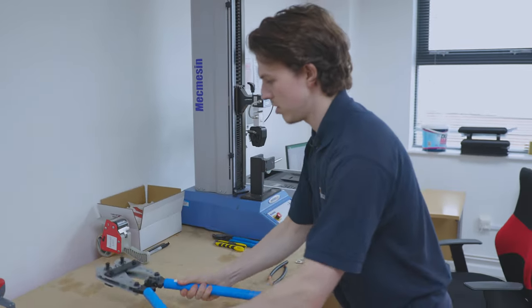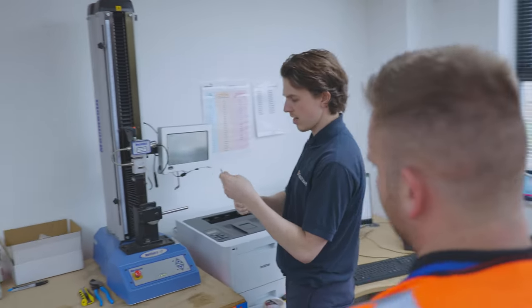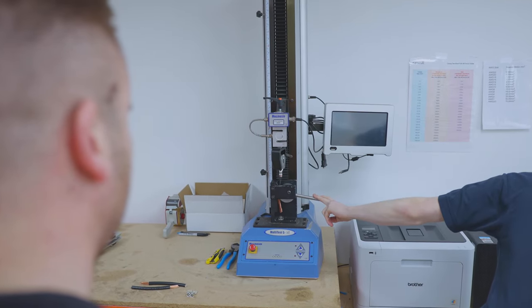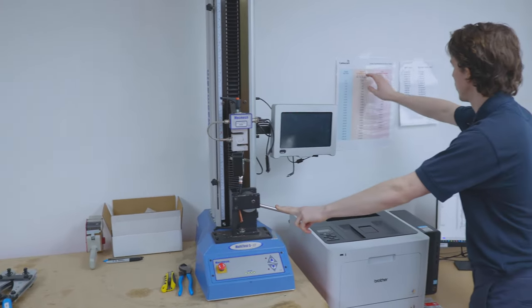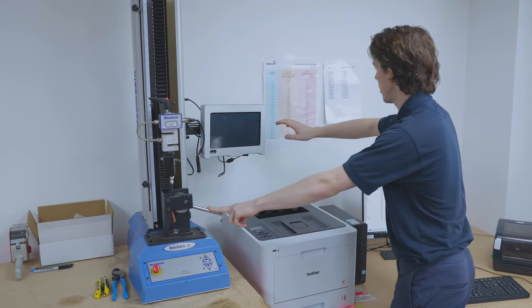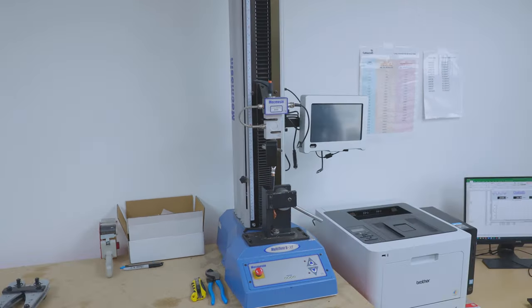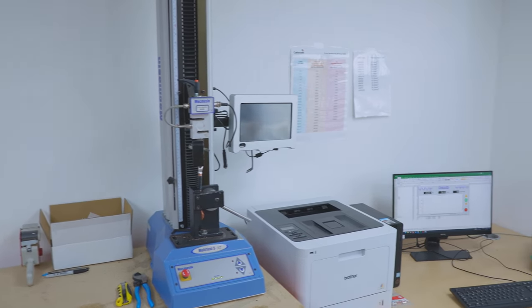We're going to run it through the calibration. So this machine is a pull-off test. As you'll see in a second, we're going to place it in the machine nice and firm. So we're just going to hold it down and we're going to start the test. We have a chart here. So this is to the British standard, which we run all our tests to, unless it's stated otherwise. So that's 35mm there. It has to get up to that number, 2100N. As that's pulling off, there we go.